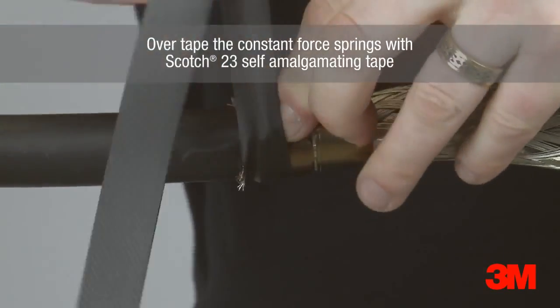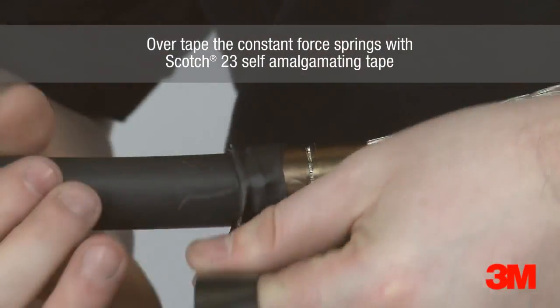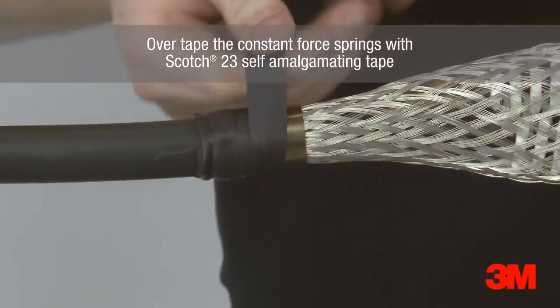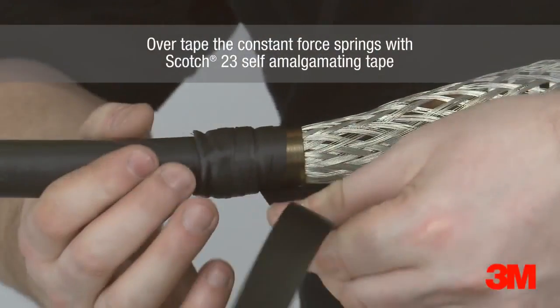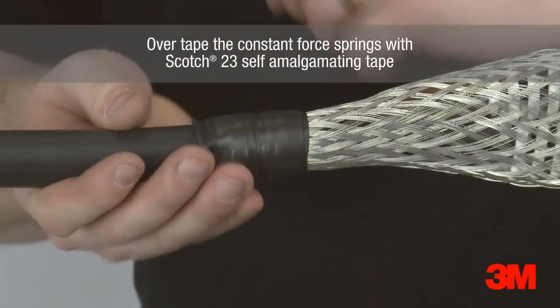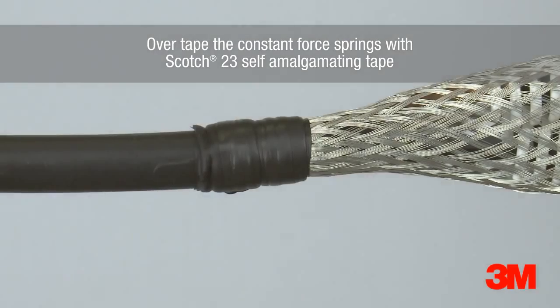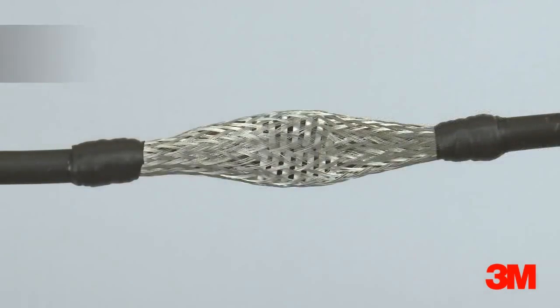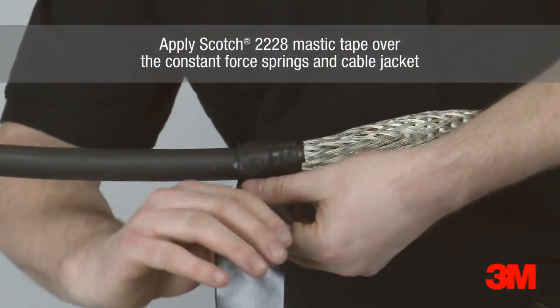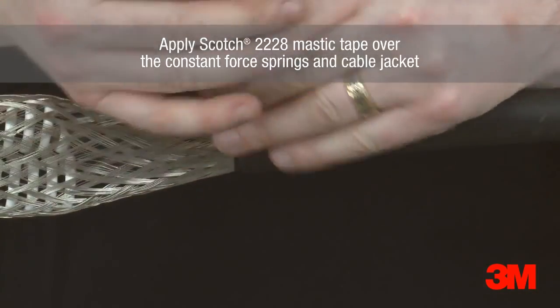Scotch 23 self-amalgamating tape is used to overtape the constant force springs. Ensure it is applied in the same direction as the constant force spring. Scotch 2228 mastic tape is then wrapped over the constant force spring and cable jacket.